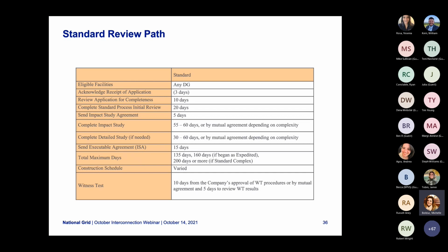We typically send the impact study agreement in 5 days. For the impact study, it can range between 55 to 60 days, or by mutual agreement depending on complexity. Similarly, with the detailed study, 30 to 60 days or by mutual agreement depending on complexity. The executable ISA goes out in 15 days, and the total maximum days you can expect is 135, 160 if it begins as expedited, or 200 days or more if standard complex.